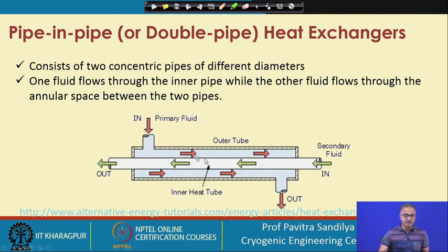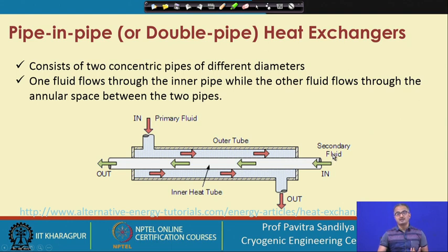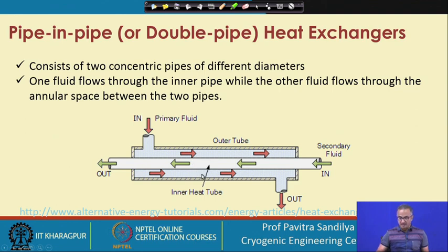One fluid flows through the inner pipe while the second fluid flows through the annular space between the two pipes. The primary fluid may be the process fluid and the secondary fluid is the utility fluid. If the primary fluid has to be heated, the secondary fluid must have a higher temperature; if it needs to be cooled, the secondary fluid must be at a lower temperature. The two fluids take different control volumes for their passage — that is how pipe in pipe heat exchangers are constructed.